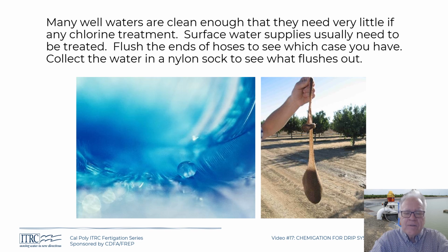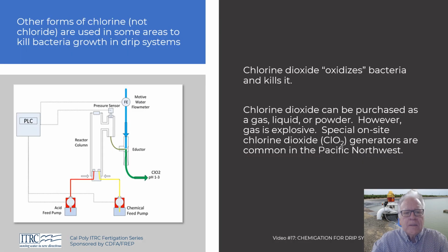And if you find out there's all sorts of bacteria, sludge that comes out, you say, well, looks like we're not injecting enough, either not frequently enough or at a high enough rate. So that's the way you do it. There is no universal answer to concentrations and frequency.